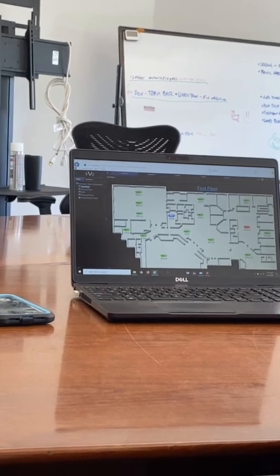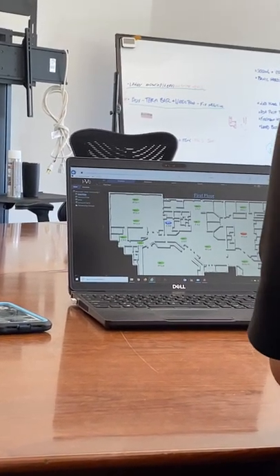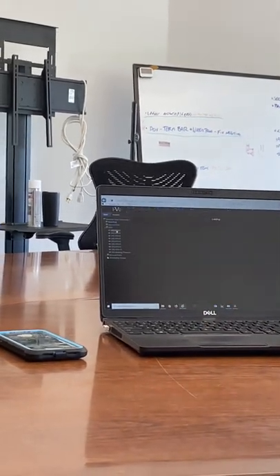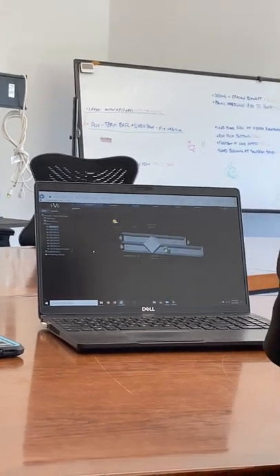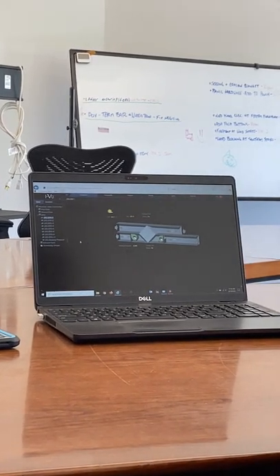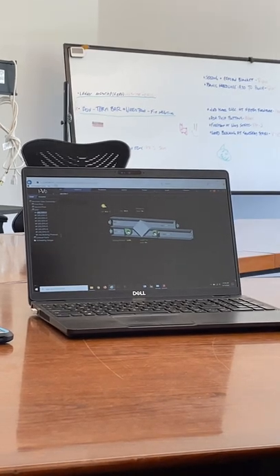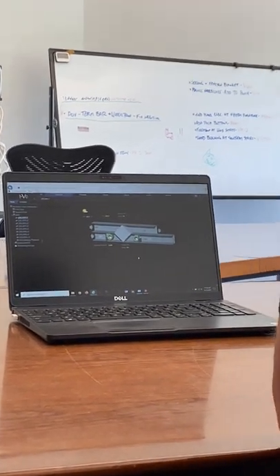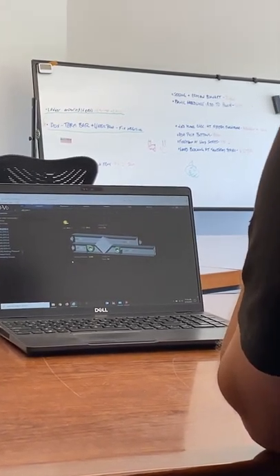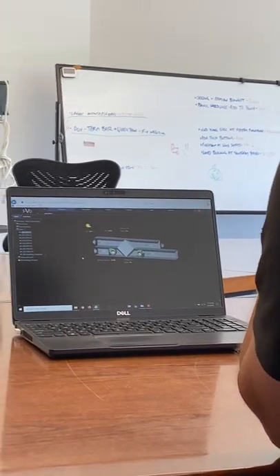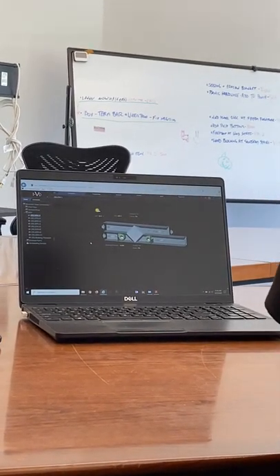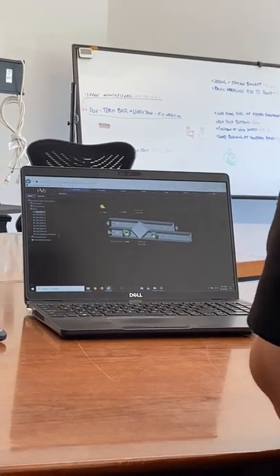Any questions so far? Question about the RTUs — you've got the ERVs attached to them. Is there a separate way to look at those? Yeah, over here on the side I have the ERVs. We're basically just monitoring, but we are enabling them based off building pressure and RTU mode — there was a sequence for those. So this is the graphic we came up with, and there are a ton of alarms associated with these.